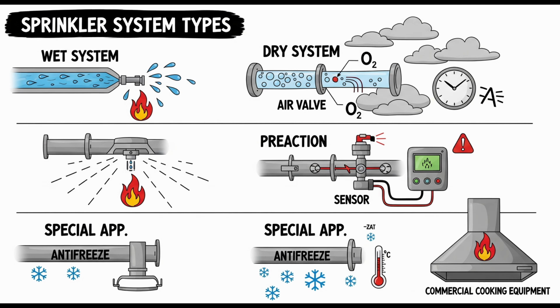Wow. We have certainly journeyed through a surprising and incredibly detailed number of specialized fire protection systems today, all guided by the requirements within NFPA 13. We really have. We started with the familiar wet pipe system, but even there we found fundamental requirements for gauges, relief valves, and clever details like that necessary air vent in metallic systems. Then we spent significant time navigating the world of dry pipe systems, designed for cold environments, exploring the complexities of sizing based on volume or delivery time, the role of quick-opening devices, the critical management of dry air or nitrogen supply, and the vital engineering principles focused on preventing ice plugs, including those recurring tiny purposeful holes in check valves.